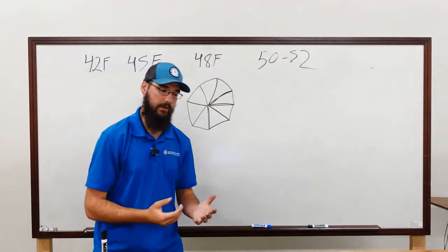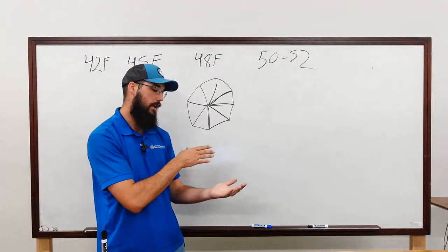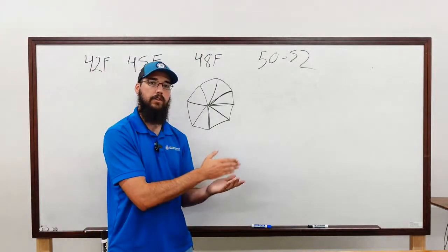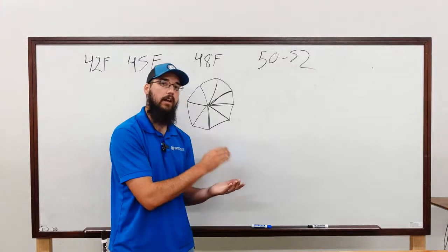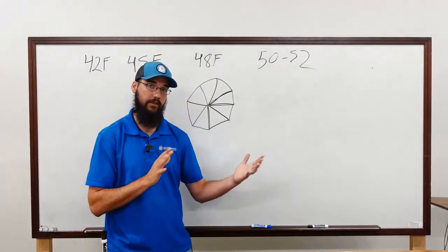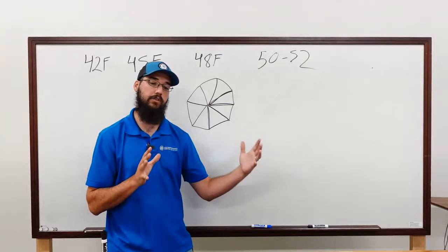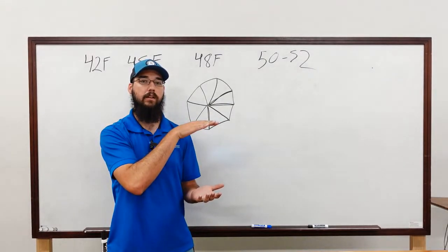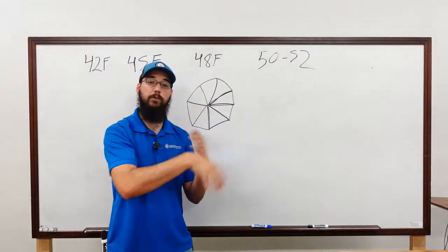So with that example, the lead chiller isn't going to tell the other chiller to turn on until after it knows that all of its available circuits, not just both, have fully staged up. And then that's when it's going to call for it.